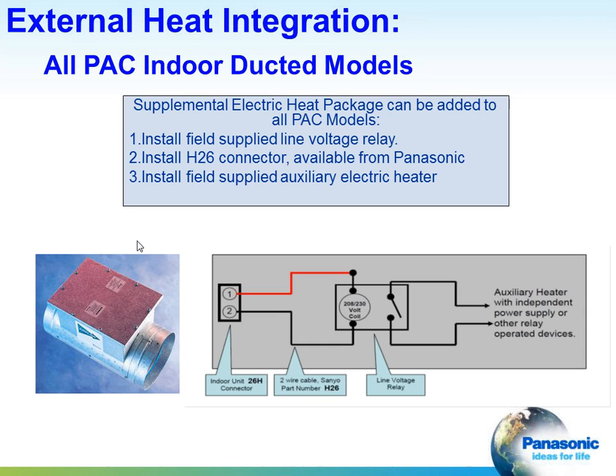I mentioned a little while ago that you probably cannot rely on this as the sole source of heat, but the system does allow you to control an auxiliary heat, such as baseboard, or in this case a small duct heater here. You would need to acquire the 26H connector, and then a 2-wire cable, and that would control a relay, which would control your auxiliary heat.